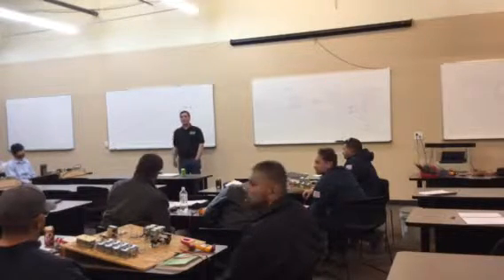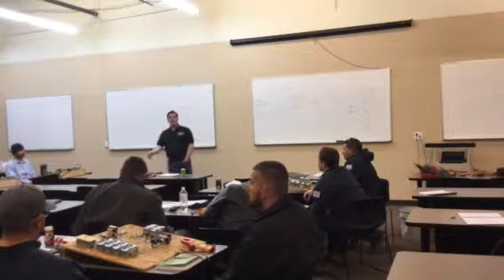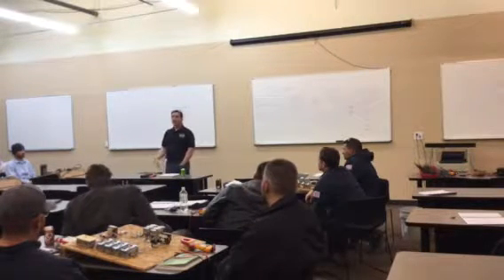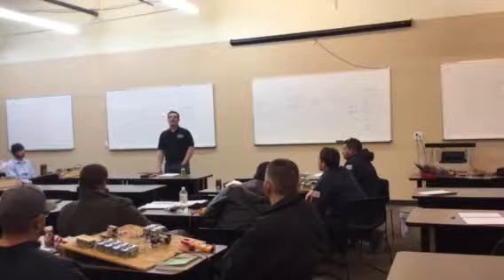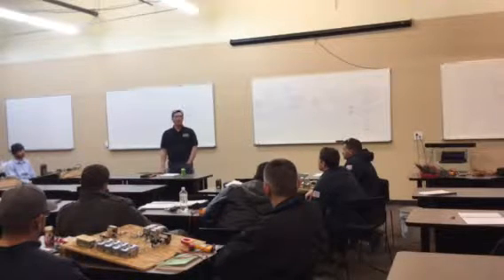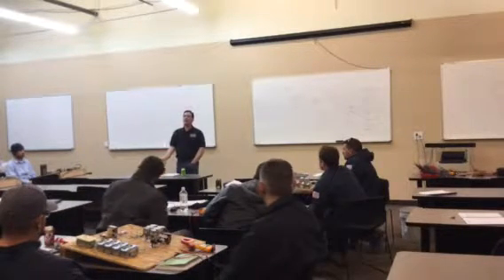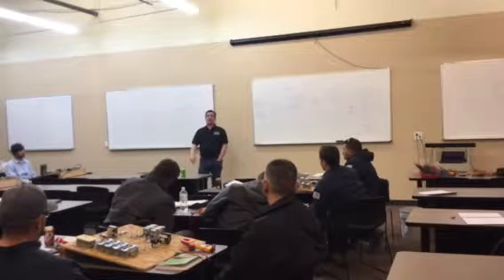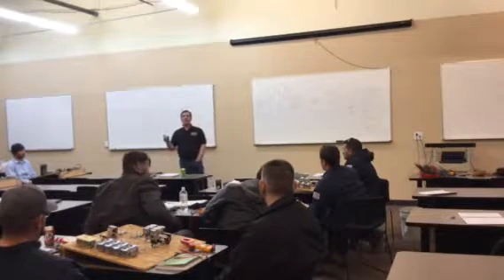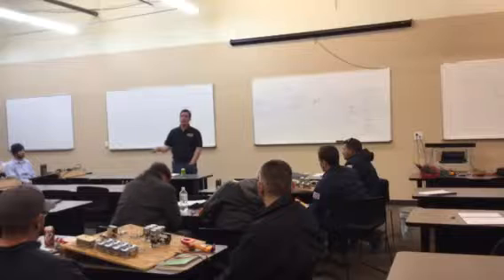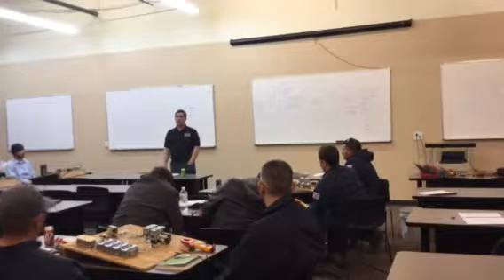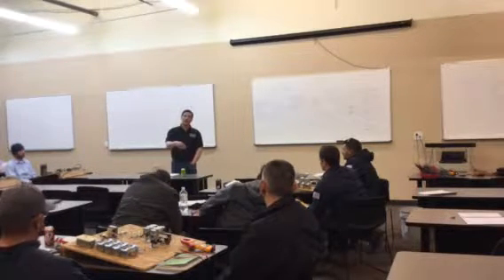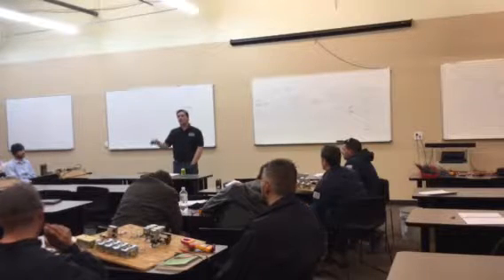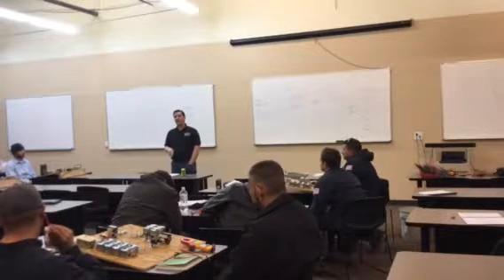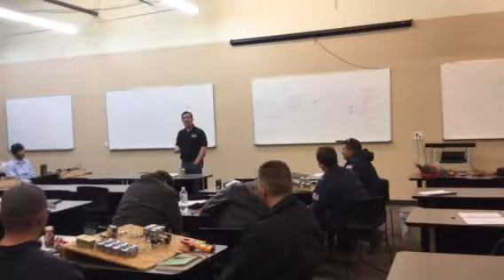Zach mentioned taking amp draws on draft inducers. When you're doing PMs, measuring this data over and over again, you might say to yourself, I keep getting the same thing all the time, why do I need to keep measuring this? What is this telling me? Well, for one thing, it's telling you that you have what you're supposed to have. And when you have something different than what you're supposed to have, you'll be able to recognize it. If you hadn't spent all that time checking things that were normal, you wouldn't be able to recognize the abnormal thing. That's another reason why I do that.